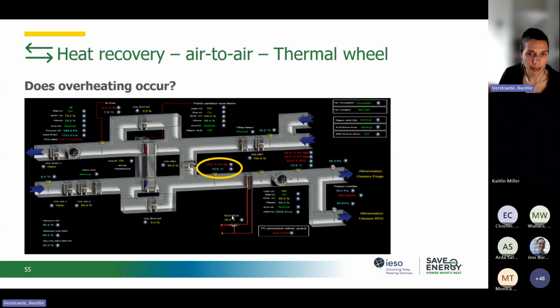In that case, as I said, the control strategy was already optimized. You have, for example, antifreeze regulation. You have a sequence for enabling or disabling the thermal wheel. And you also have an optimized sequence to control bypass dampers in the fresh air and the exhaust air duct. With all that control strategy, you can modulate heat recovery and meet the right supply air temperature.